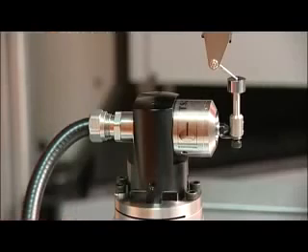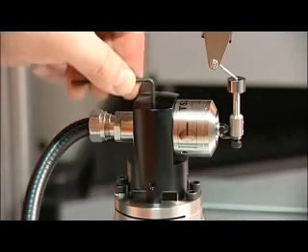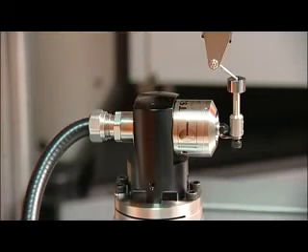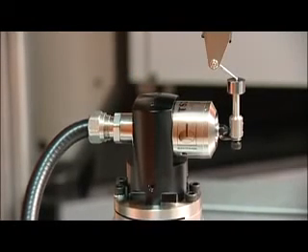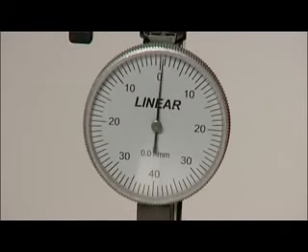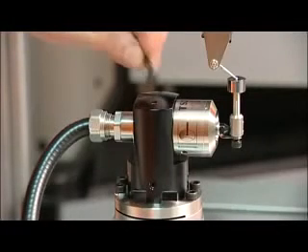The side to side adjustment is provided by the two grub screws mounted on the top of the TS27R body. These grub screws oppose each other and require one to be loosened while the other is tightened. This can be an iterative process.